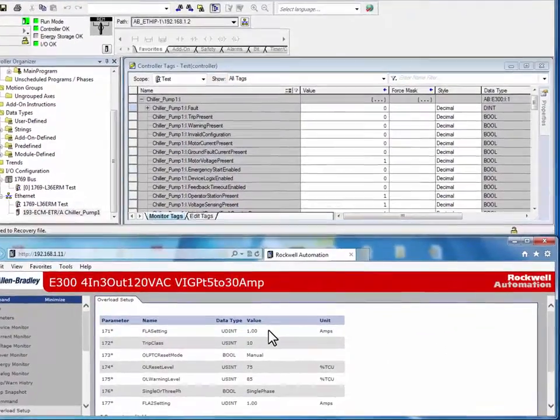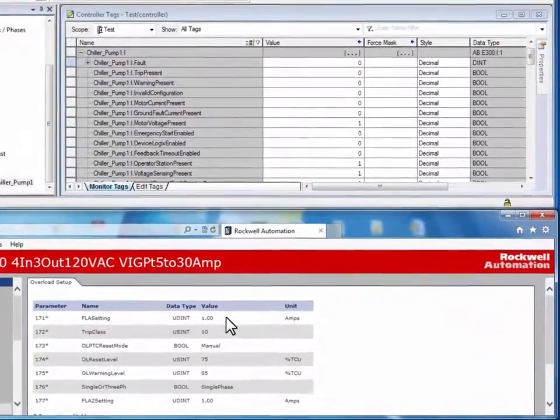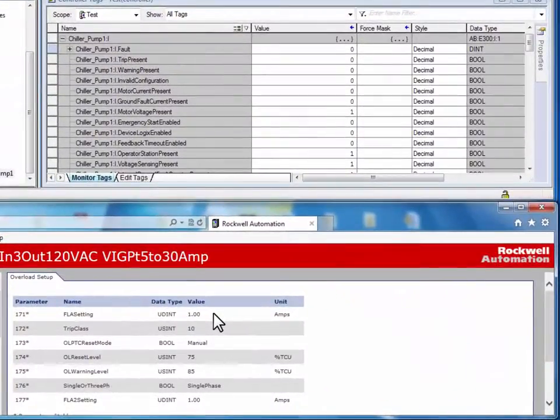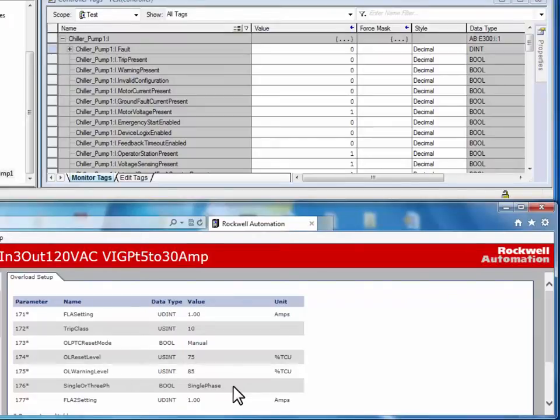The default FLA setting changed from 0.5 amps back to 1.00 amps. And the single or three phase parameter was changed from the default setting of three phase back to the original setting of single phase.